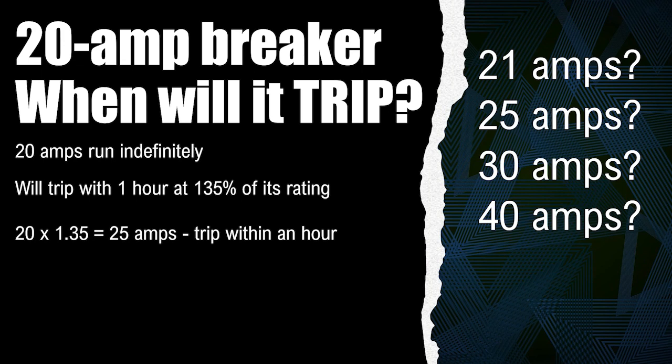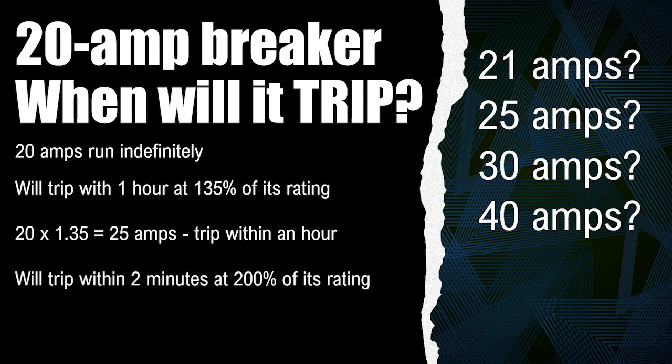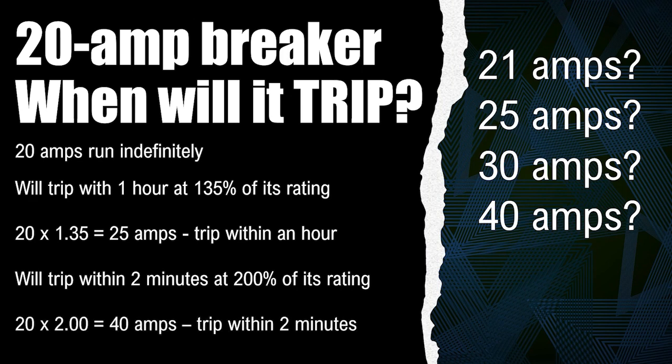The buses — all these rules are supposed to work in perfect unison in a perfect world to protect all of that. So the next standard is that it must trip within two minutes at 200% of its rating. If it's tripping within two minutes, it's doing its job. Somebody like ETL is going to put their sticker on it saying it's performing the way it's supposed to. So if we take that 20 amps and multiply it by 2.0, we end up with 40 amps, and it's required to trip within two minutes.